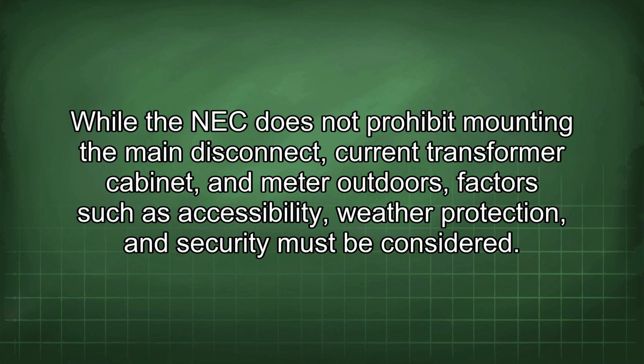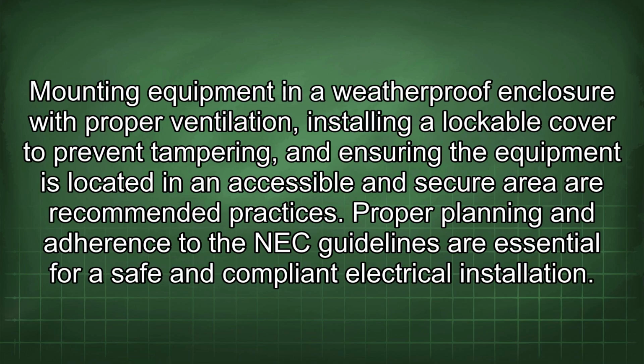While the NEC does not prohibit mounting the main disconnect, current transformer cabinet, and meter outdoors, factors such as accessibility, weather protection, and security must be considered. Mounting equipment in a weatherproof enclosure with proper ventilation, installing a lockable cover to prevent tampering, and ensuring the equipment is located in an accessible and secure area are recommended practices. Proper planning and adherence to the NEC guidelines are essential for safe and compliant electrical installation.